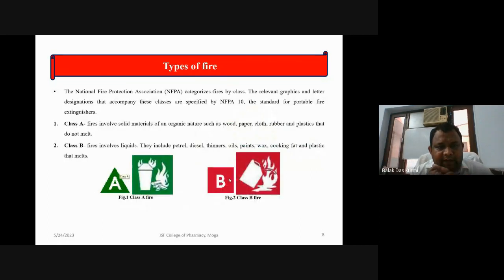The National Fire Protection Association, NFPA, categorizes fire by class, because depending on the material, the fire may be of a different type. The relevant graphics and related designations that accompany these classes are specified by NFPA 10, the standard for portable fire extinguishers. So let's discuss class A fire. On the basis of class, we can choose the fire extinguisher or fire protection system. Class A fire involves solid materials of organic nature such as wood, paper, cloth, rubber, and plastic that do not melt, or we can say these types of material ignite in the presence of oxygen and heat.